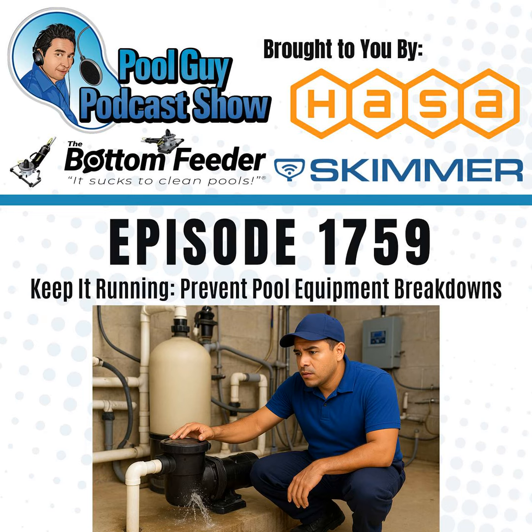And heaters, I can probably spend the whole podcast on heaters, but there are some basic things to check. The igniters are what wear out the most in the heaters. So the first thing when the heater's not igniting, I would definitely check the igniter first. That's always usually the first problem, because that's a pretty common wear part. There are other problems also. I guess before you check the igniter, make sure the gas line is actually on. A lot of times the gas line is off. The little handle is turned off.